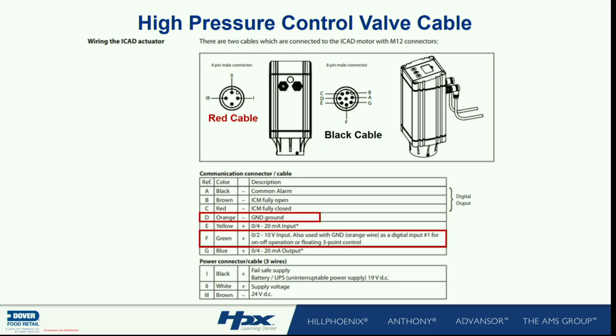Does anybody know what the maximum operating pressure of the vessel is? It's set up in that controller. Depends on the controller, but you can change it. This one is 40 bar. 580, right? So what does that mean? If you lose the rack in the middle of summer and that vessel pressure rises to 600, you're gonna pop off. Not yet, because it's 650. But that controller is now going to go into safety mode. It's going to say, I can't control my vessel pressure, so it's going to shut the high pressure down. High pressure valve is going to go, rack's going to pop off on your discharge.